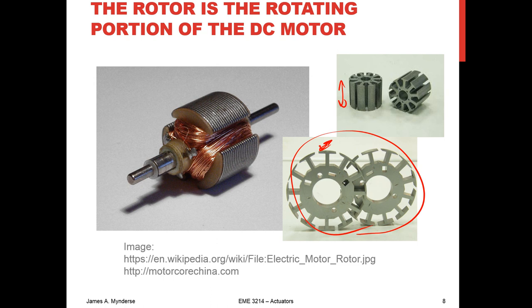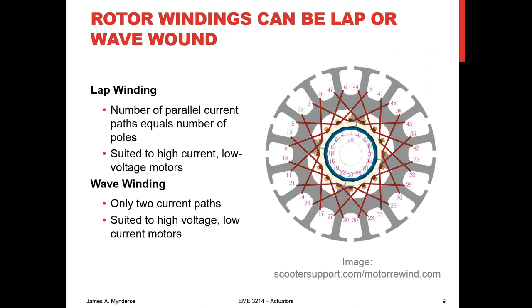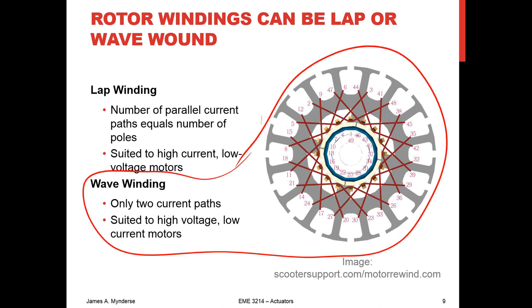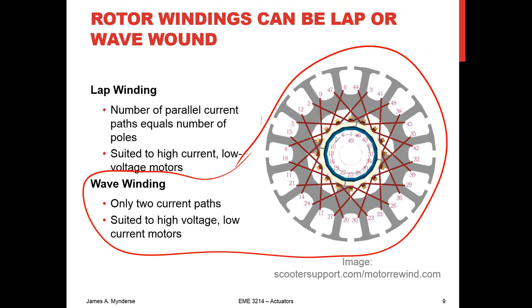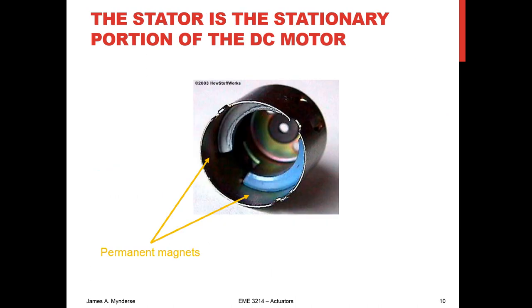The coils of wire can be either lap or wave wound. In lap winding, there are as many parallel current paths as there are poles. In wave winding, there are only two, with much more complicated paths. Lap winding gives high current, low voltage motors. Wave winding gives high voltage, low current. It depends on the wire choice you use, how much wire you have, and your resistive heating.